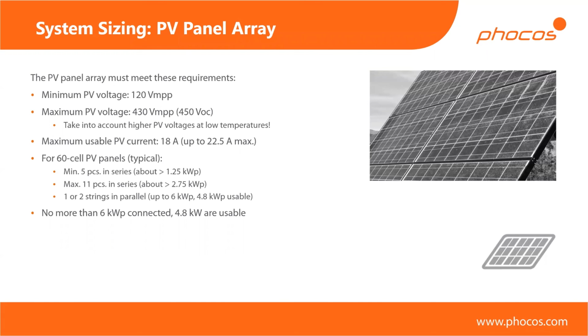For the PV array, the PV array must meet these requirements, and if it does, then it's automatically good for the system. This is specific to the 48 volt models. Obviously, there's only small minor differences for the 3 kilowatt 24 volt model. Namely, the minimum PV voltage is lower for the 3 kilowatt model. It's 90 volts MPP instead of 120 volts.